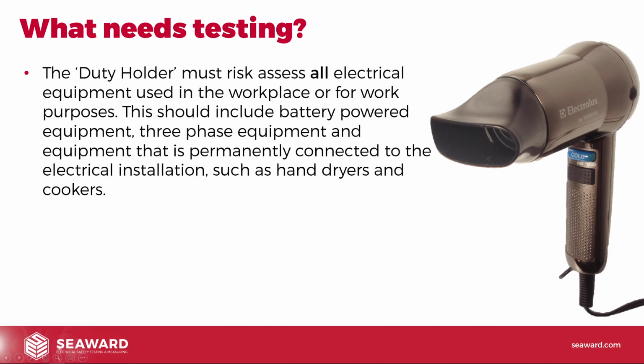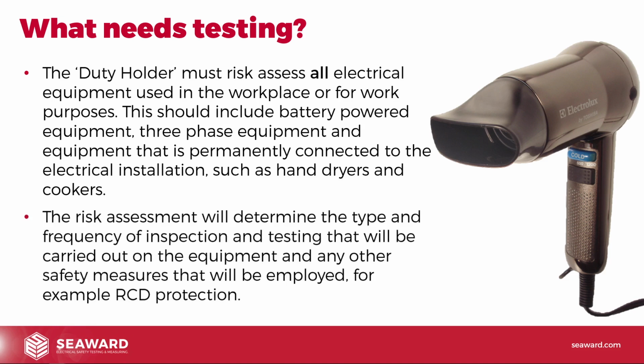So the duty holder must risk assess all electrical equipment used in places of work or for work purposes. This should include battery powered equipment, three-phase equipment, and equipment that is permanently connected to the electrical installation, such as hand dryers and cookers. Again, often these things get missed out. The risk assessment will determine the type and frequency of inspection and testing that will be carried out on the equipment and any other safety measures that will be employed, for example, RCD protection.